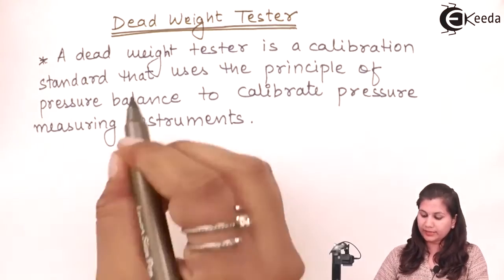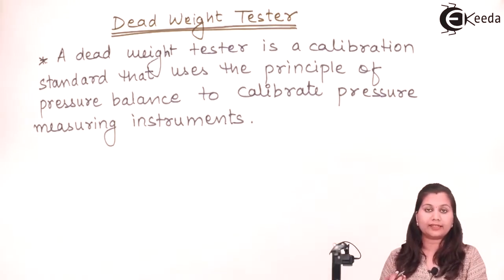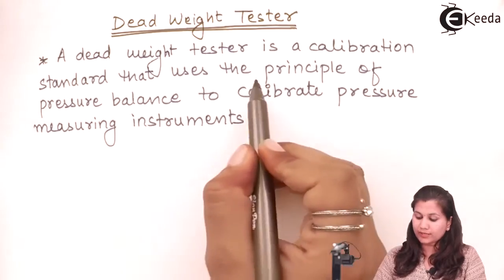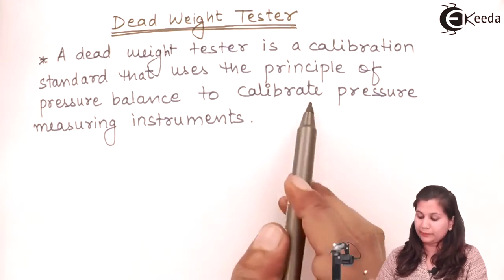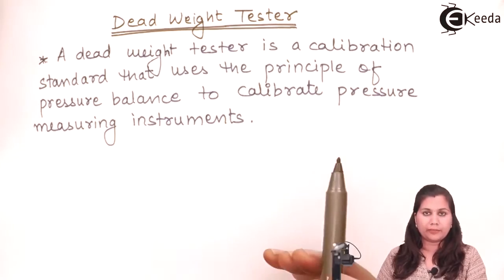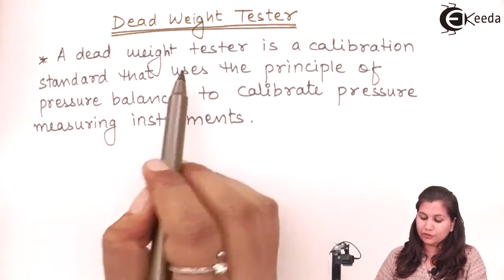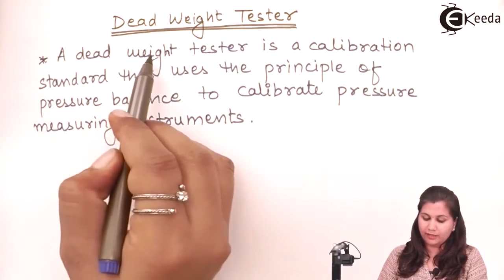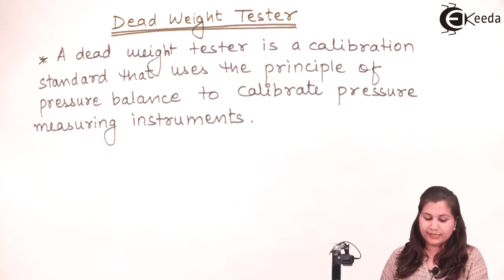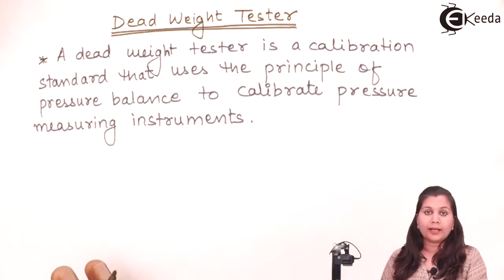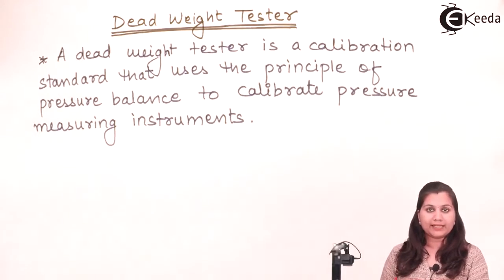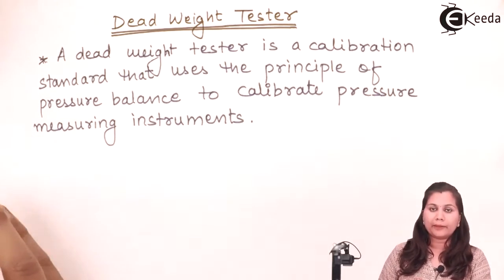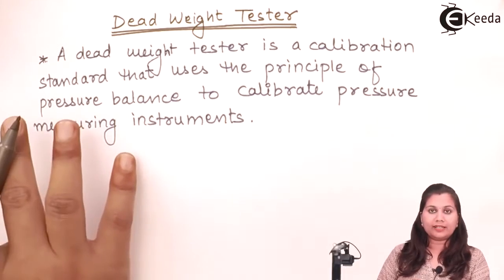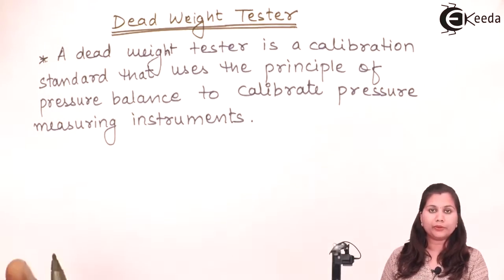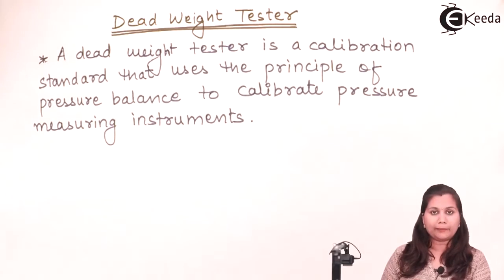So the deadweight tester is a calibration standard, or a calibrating device, which uses the principle of pressure balance to calibrate pressure measuring instruments like pressure gauges. It uses calibrated weights, and these calibrated weights apply a known pressure to the device under test, and by equating or balancing these pressures, it calibrates the pressure measuring devices. So the deadweight tester is both a pressure measuring and pressure producing device, also called a calibrating device.